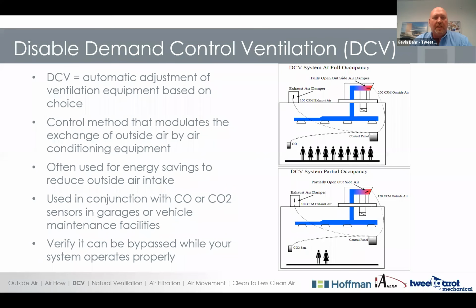Another recommendation is to disable your demand control ventilation. Demand control ventilation can be seen in multiple facilities. It could be in your office facility, or it could be in a municipal kitchen or municipal garage, county garage, repair facility where vehicles are present, in a kitchen. It is an energy saving aspect that has been strongly used over the last 10, 15 years. In traditional spaces of offices, they utilize sensors, carbon dioxide sensors. As the level of carbon dioxide increases, the amount of outside air increases. These are code compliant systems of manipulating and monitoring the amount of outside air that you bring into your facilities.